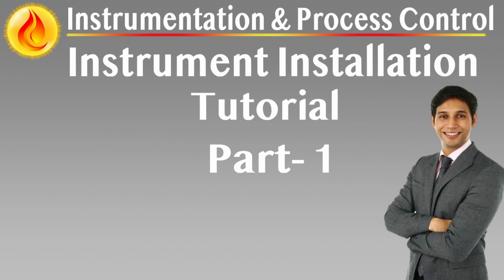Installation of online instrumentation, a tutorial: integrated design philosophy for operational accuracy and maintenance access. System overview and design intent. Installation of online instruments must be strategically tailored to ensure accurate process measurements under all expected normal and abnormal operating conditions. Optimal instrument hookup configurations are to be selected based on measurement integrity, lifecycle cost, and ease of maintenance. Heating, insulation, sealing, and purging techniques must be judiciously applied only when alternative hookup strategies offer less attractive trade-offs in terms of total cost of ownership, TCO, operational accuracy, or maintenance complexity.